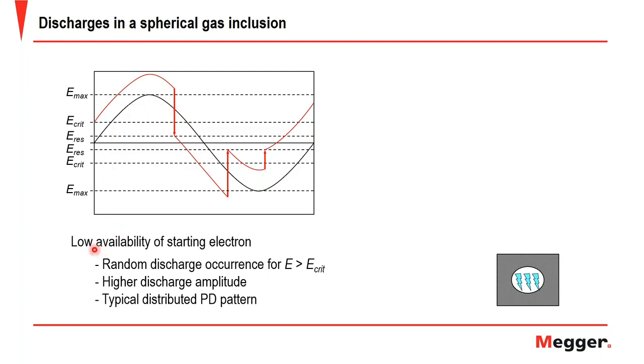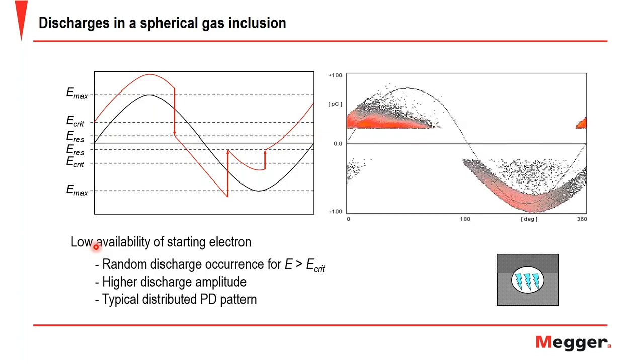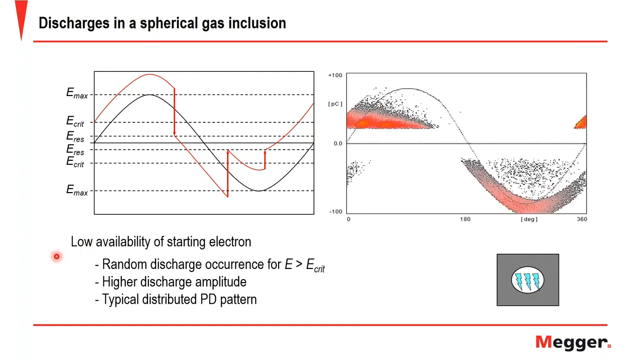And in this case of low availability of free electrons, the electrons start the avalanche after that time lag that's derived from the natural radioactivity that causes this delay. And here we have the typical phase resolved partial discharge pattern for such a case where we have a higher amplitude and this lower availability of starting electrons.